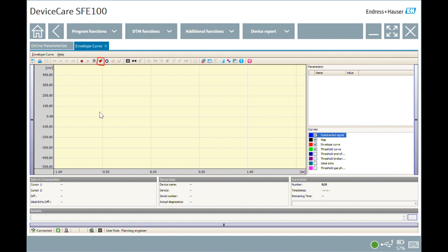What I'll do is start at the first one and click through them. As you can see, you can witness the curves moving, and it looks somewhat like a video. Recording multiple curves like this is a powerful way to troubleshoot what's happening with the process. In this example, the customer is draining the tank to see when their level crosses the threshold and when they're going to lose their signal. We were having issues in this particular install, and recording multiple curves like this really let us troubleshoot by seeing inside the process at a continuous level.